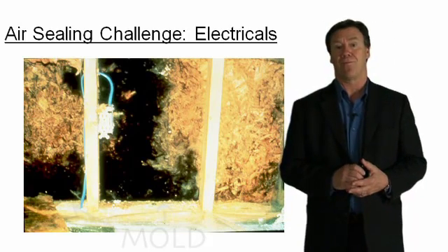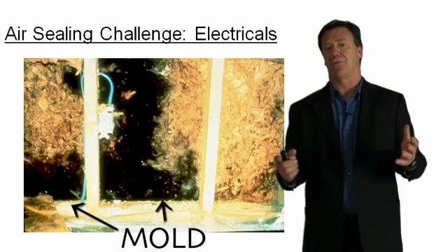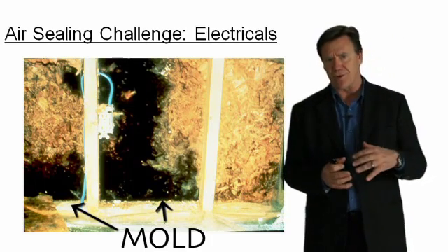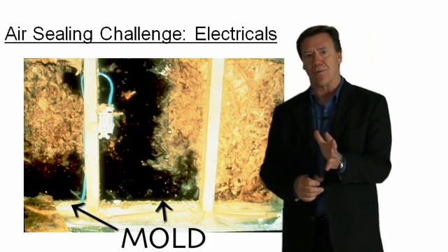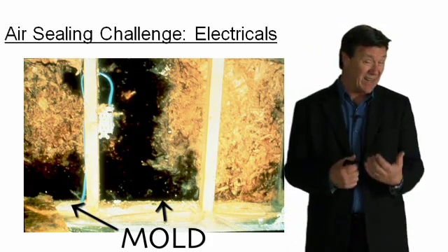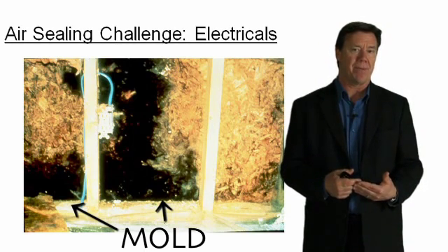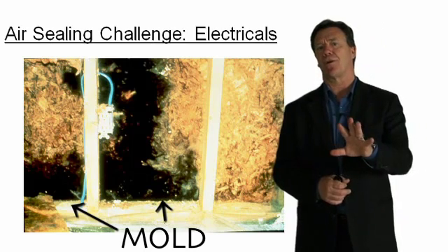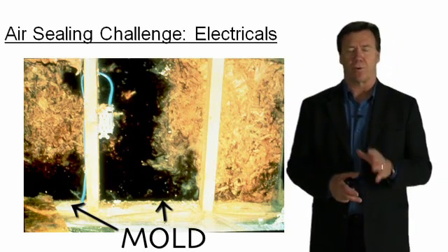Here is a great example of what can happen with uncontrolled air exfiltration. As warm, moist air exfiltrates through an opening in the wall, it contacts the cold OSB, condenses, and over time moisture builds up — and mold will start to grow. Any time you have a surface relative humidity above 70%, those are prime conditions for mold growth.